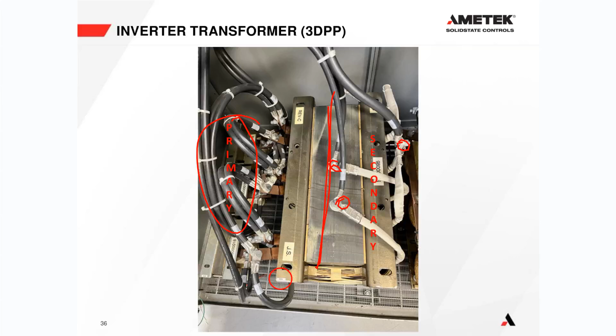Once again, it's an isolation transformer, so it gives us isolation. If there was a fault in the inverter bridge for some bizarre reason, and DC got onto the primary of the transformer, because of the isolation, that DC would not be allowed to propagate onto the secondary terminals. You would not get DC going to your output circuits, which could damage equipment and cause a whole load of issues. So the isolation means the DC cannot propagate from the primary to the secondary.